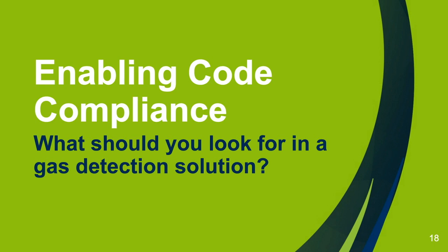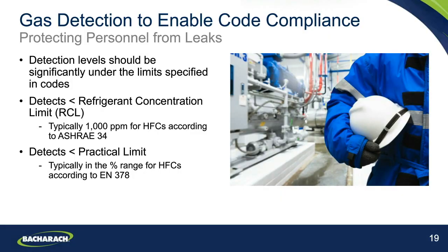So we'll touch on here what you should look for in a gas detection solution to help enable compliance with the codes. Now, there are lots of gas detection products available on the market, but there are some key factors to consider when looking at the specifications and selecting something to use. We of course need to ensure that the detection levels available on the device are under the limits specified in the codes, and we would advise that you look to make sure they're significantly under those limits as well, because then you allow for tolerance within there, and you can ensure that you're on the right side of safety by alarming before you ultimately have to from a code perspective.